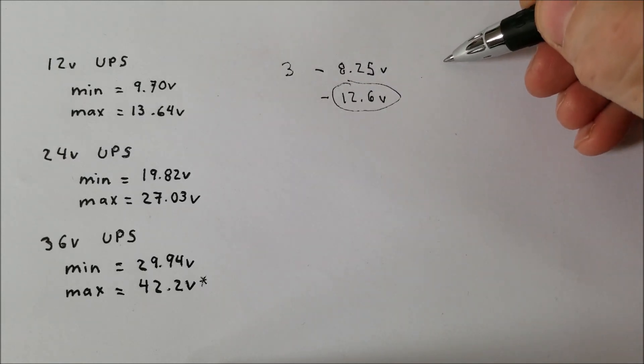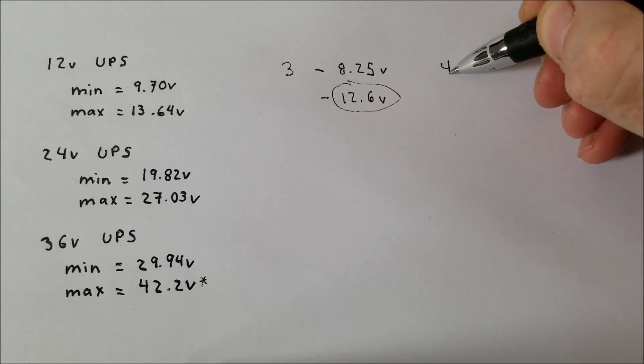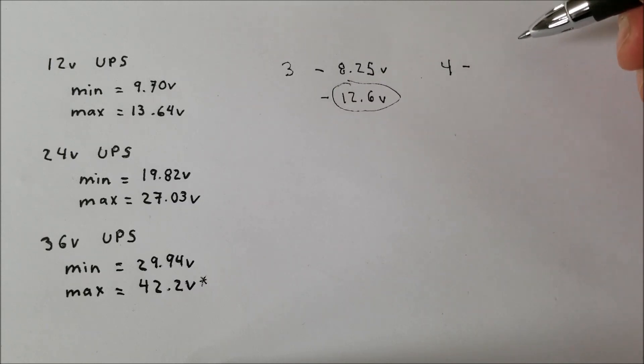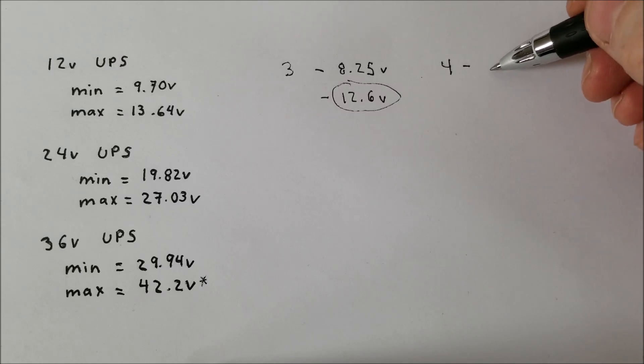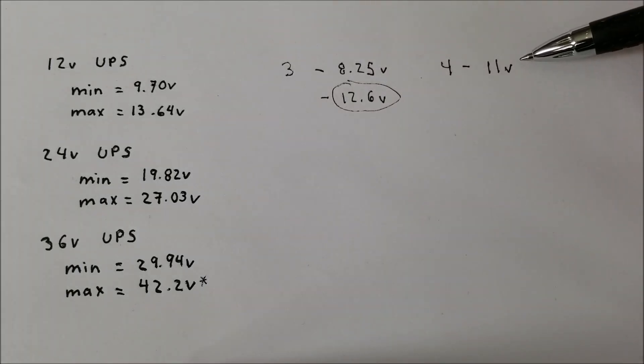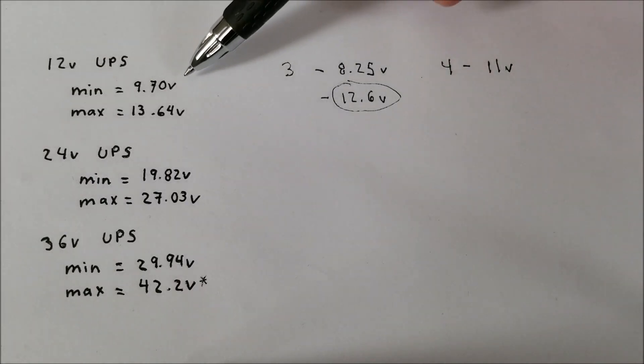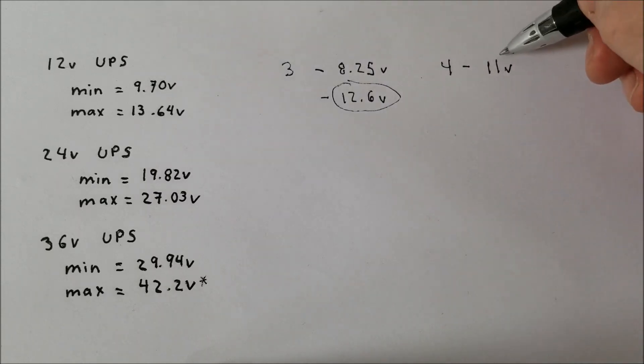Now let's see if we do 4 cells in series. So we do 4 cells in series and we multiply that by 2.75V for the minimum. We obtain 11V. And as you can see here, now this becomes the problem because the minimum voltage is 11V whereas the UPS goes down to 9.70V. So again here, we have a problem. This will not work.